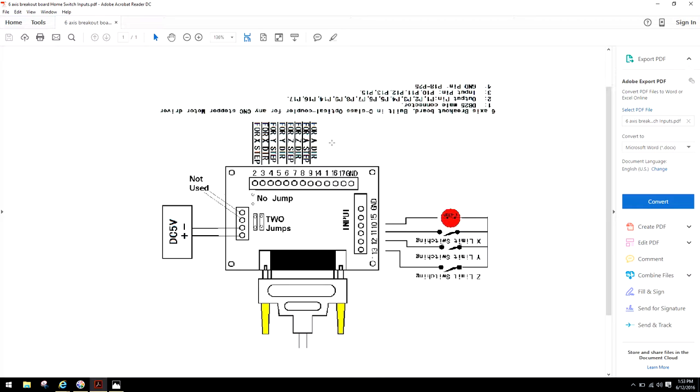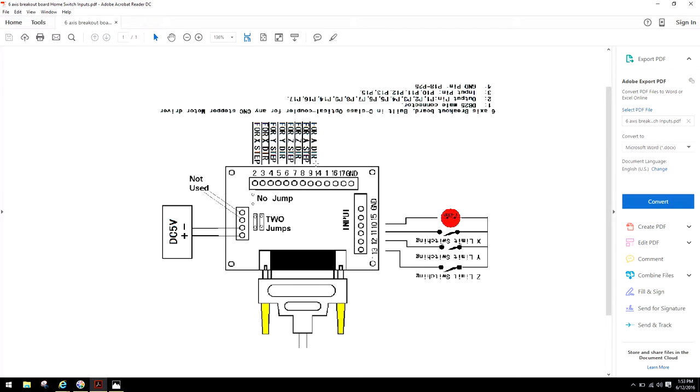What you'll notice, and this is where the problem starts, is there's only one ground terminal, which means in order to do this, you would be hooking up each driver together into this ground and then splitting it on the end of the driver. Guys, that is incorrect. That is called daisy chaining, and that is not best practice. I've seen it on YouTube enough where guys are showing their system. They'll daisy chain drives together, whether it be power, whether it be ground, whether it be signals. That is not the proper way to do it.